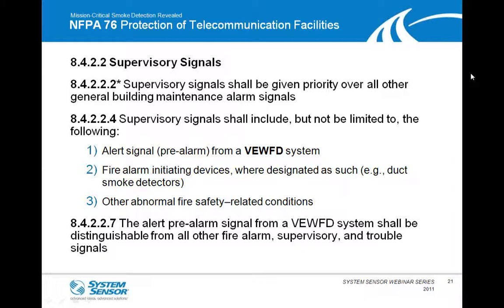And then again, it does allude to fire alarm initiating devices that are more specifically designed for supervisory signals, such as a duct smoke detector. Duct smoke detectors are more so there, or are supposed to be there, for supervisory concerns rather than evacuation or alarm events. However, again, it depends on the code and the jurisdiction. Oftentimes, duct smoke detectors can be used as that evacuation device as well.